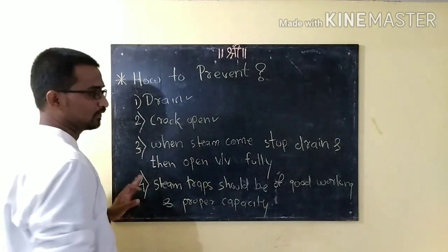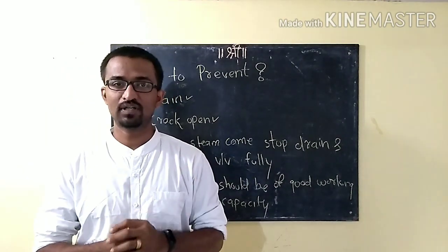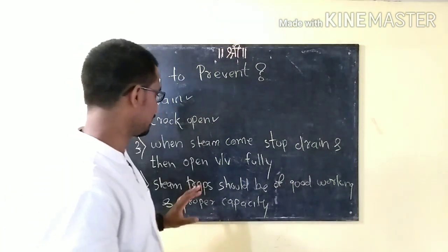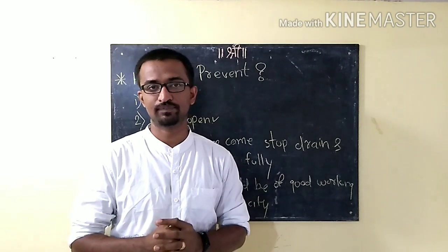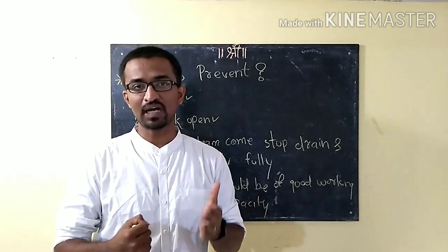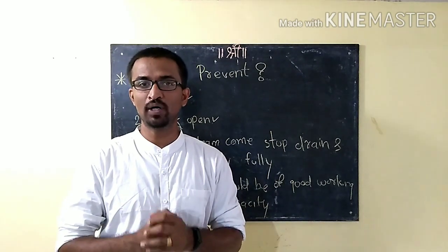Then second thing, your steam traps. Steam traps also matter in case of water hammer. Your steam trap should be in good condition and of the perfect size. And apart from this, during the design stage, you can avoid sharp bends, you can reduce the number of joints, so that the water hammer possibility will get reduced.